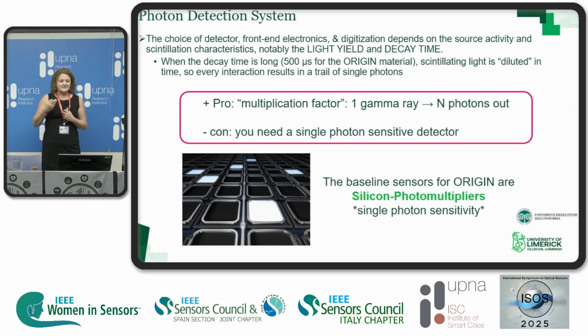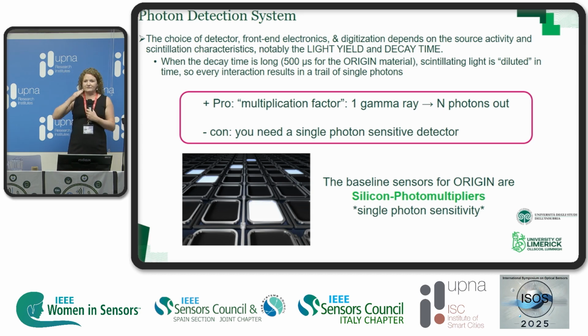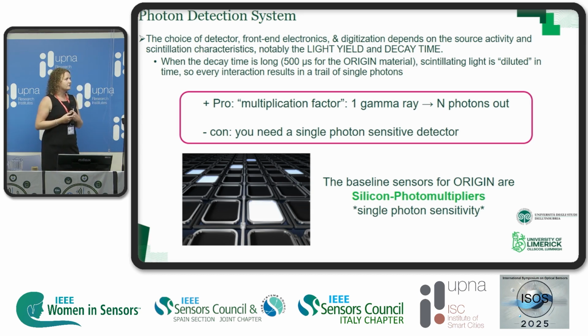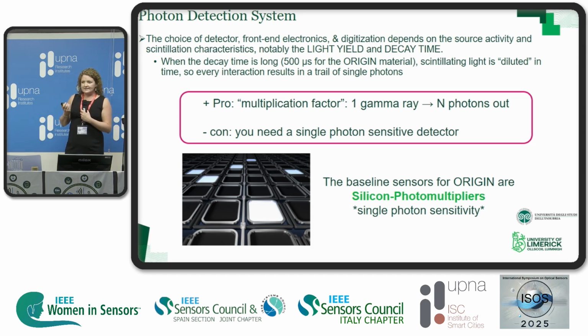And this is really determined by the scintillation characteristics, especially the light yield and the decay time. In the case of the materials used for Origin, we have a really long decay time. So this effectively means that we're diluting that scintillating light. For every interaction, we have a trail of single photons. The advantage of this is that we have that multiplication factor: for every gamma ray, we have multiple photons coming out. But on the other side, we have the need for a single photon sensitive device.